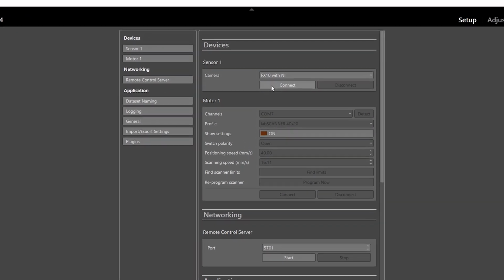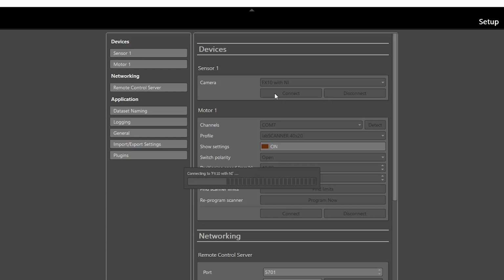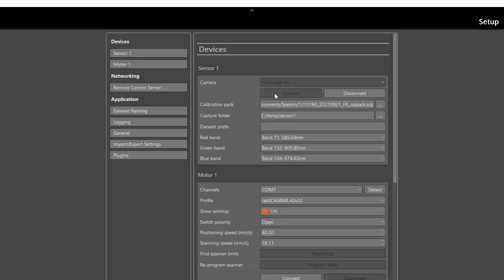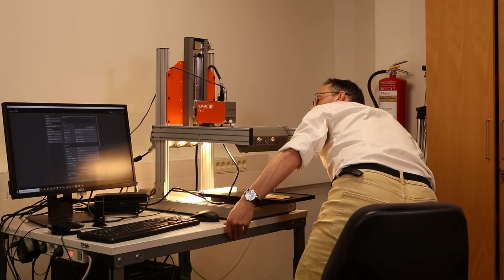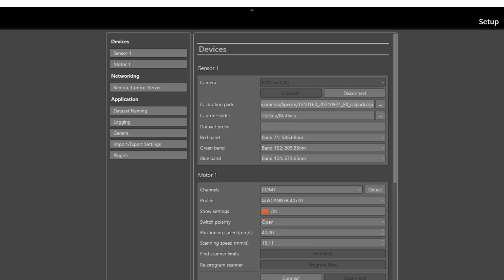So first of all, you connect with the camera. Here it's going to be an FX10 between 400 and 1000 nanometers, connected with the National Instruments grabber to the computer. This is a Camera Link camera, but we also have the GigE version. Once you are connected like this, you need to load the right calibration pack. Notice that here it has a serial number, so I will check from the camera, 1210160, and it matches the spectral calibration pack, the serial number and also the date. Notice that when the calibration pack includes FX in the naming, that means the automatic image enhancement routine will be run in the camera to unify the spectral calibration between all the cameras and also to correct the smile and the keystone.